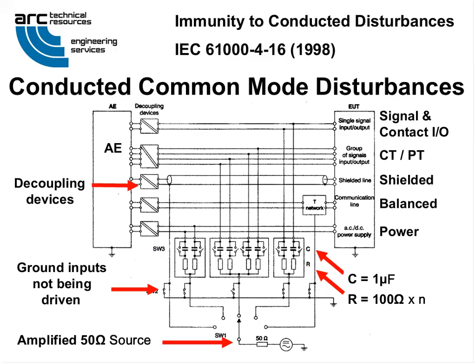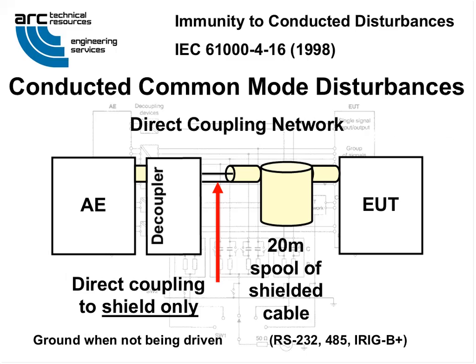Test setup requires that the signal and contact I/O, CTPTs, shielded, balanced, and power ports of the EUT all be outfitted with couplers and decoupling devices before testing begins on any of them. An amplified 50 ohm source, like I showed you, supplies voltage to the coupling networks that are shown here. You ground the inputs to the coupling networks that are not being driven. So you have to get the EUT to survive being connected to the coupling networks. Now that it's working normally, we can open one of them and begin testing on the port. That's how this is done.